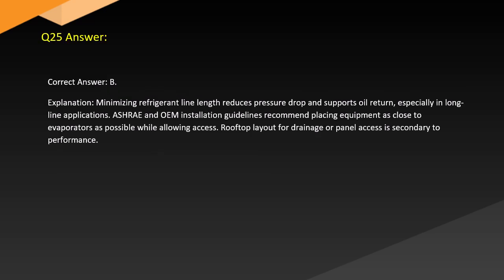Answer. Correct answer: B. Explanation. Minimizing refrigerant line length reduces pressure drop and supports oil return, especially in long line applications. ASHRAE and OEM installation guidelines recommend placing equipment as close to evaporators as possible while allowing access. Rooftop layout for drainage or panel access is secondary to performance.